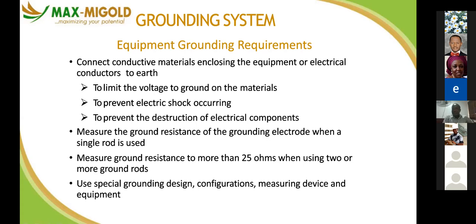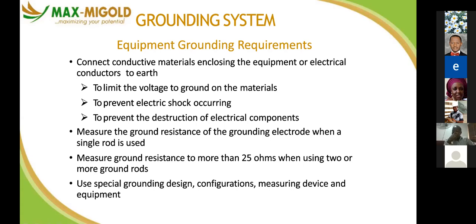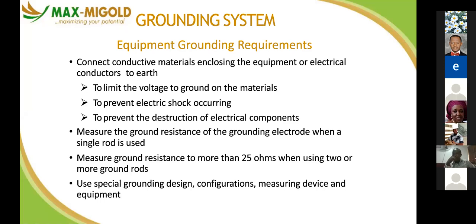So my question is, what facilities must you add earthing to? As in, is it only a generator placed outside the building? What other facilities, especially outside, must we add earthing to? Yeah, as I said in your reading manual, all potential electric conductors, not only your generator, not only your installation. If you have a communication mast in your facility, it must be earthed because of lightning.